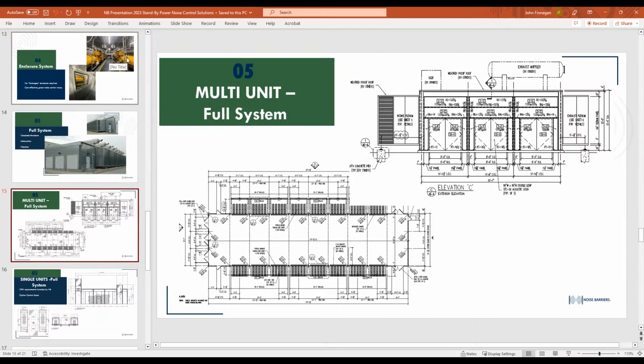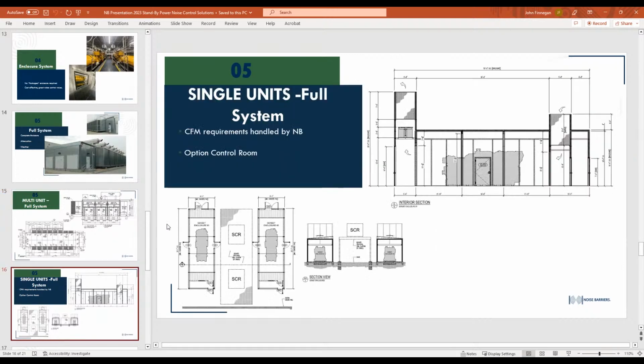It's very attractive for them to be able to walk into one room and look at everything going on with their backup power. There are no partition walls between each one; they just run straight through. Again, accounting for the airflow and the maximum pressure drop, we try to keep it about 0.4, 0.5 worst case. That's a big barn style setup, and the more typical one most people are used to is the single standby engine test cell.